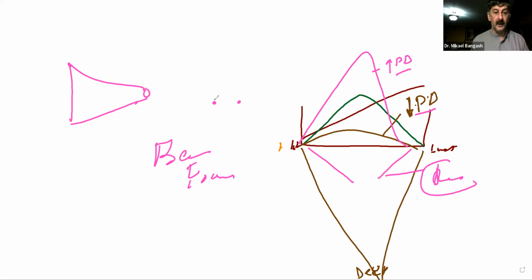If there was a greater delay, then this beam here will focus at a shallow depth. Whereas if you had a lesser delay, then overall your curve is going to be smaller. That means, diagrammatically, right, that is how the beam focuses at a deep point.